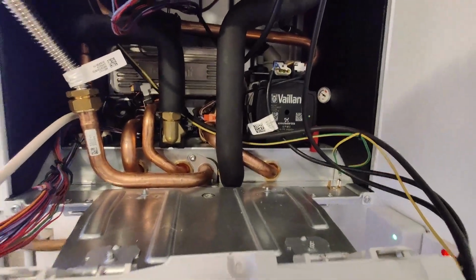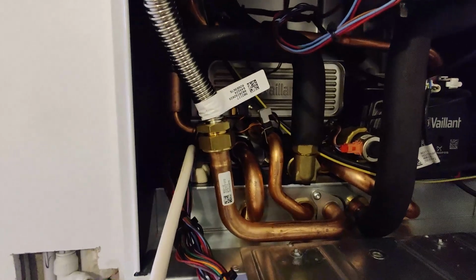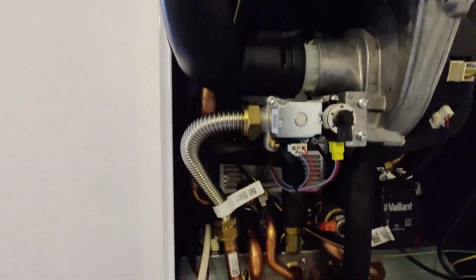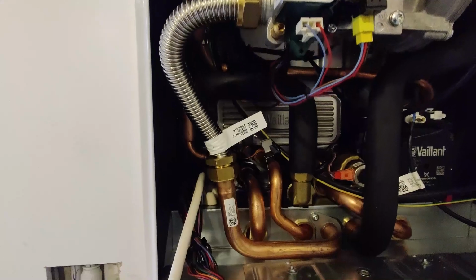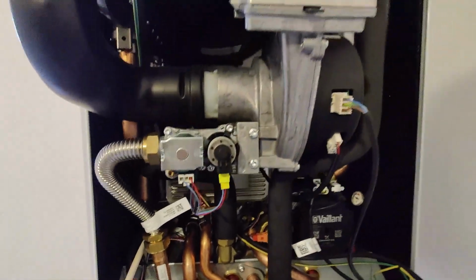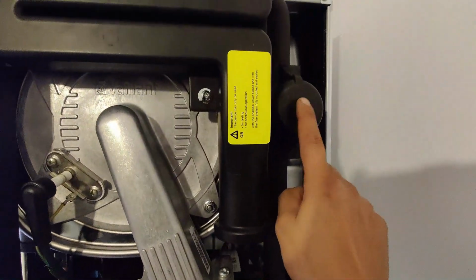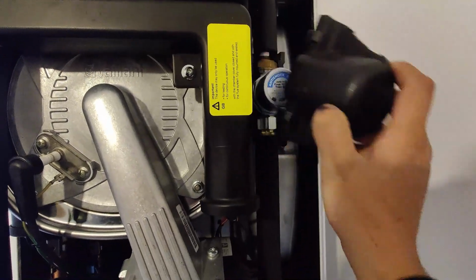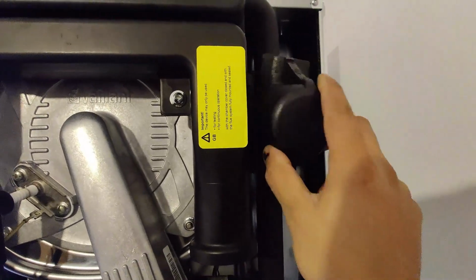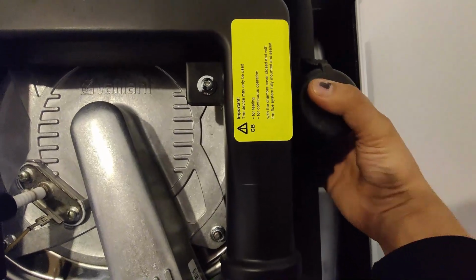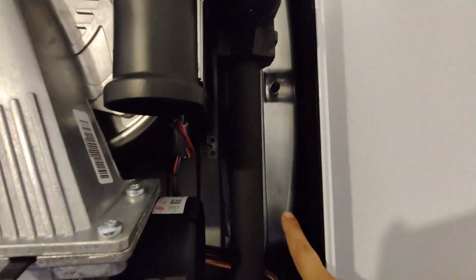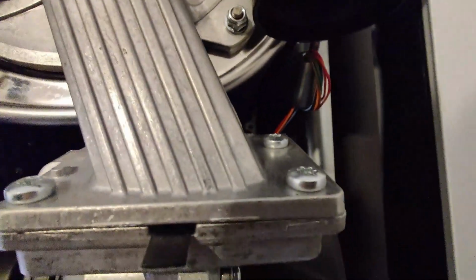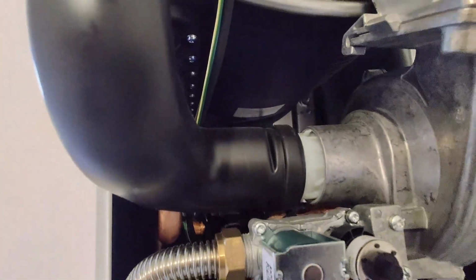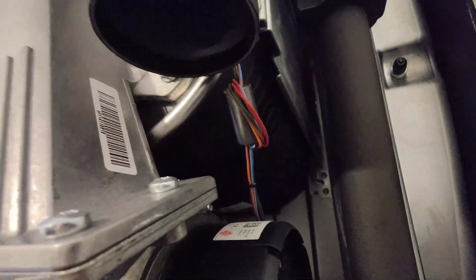So it's got the Vaillant pump, gas valve, normal typical setup in here. The only additional thing you may find is a shock arrestor that this boiler comes with as a built-in item. So that's a shock arrestor for it. A huge expansion vessel, but look at the size of this main heat exchanger. It's absolutely enormous.